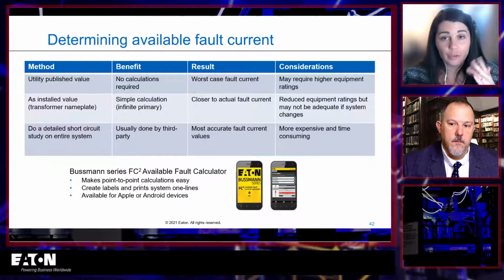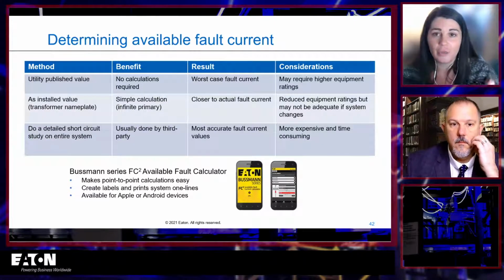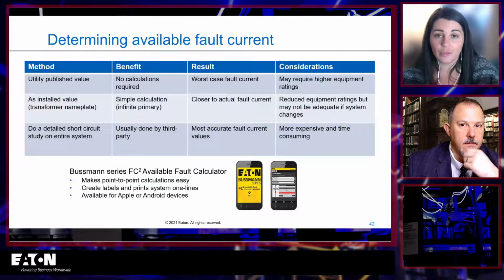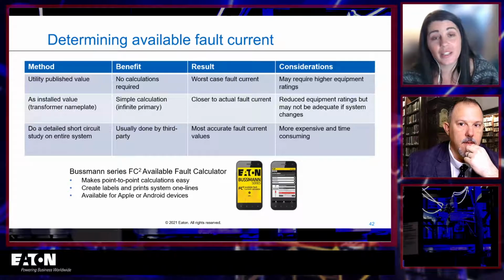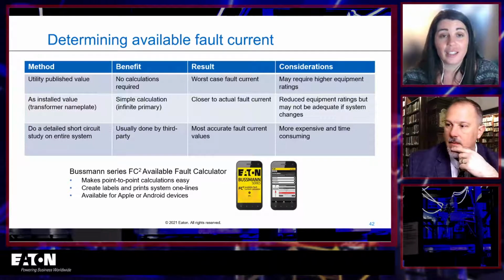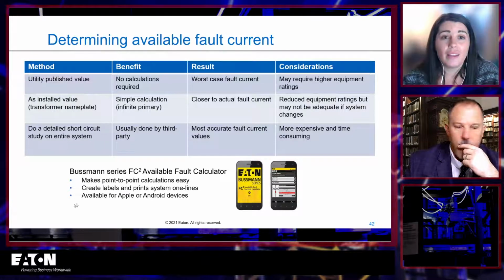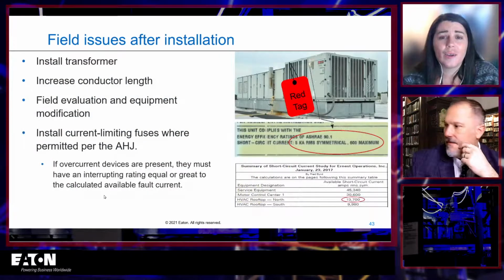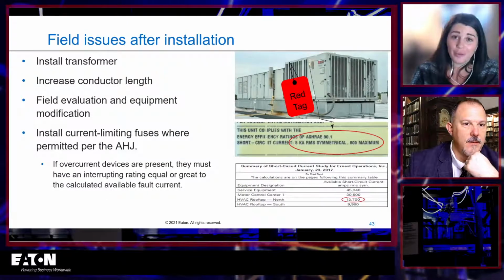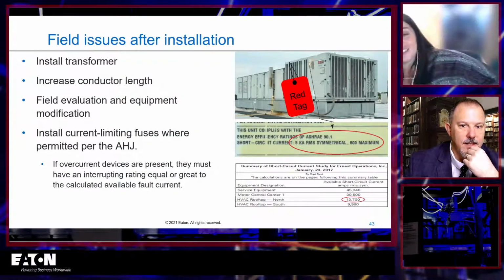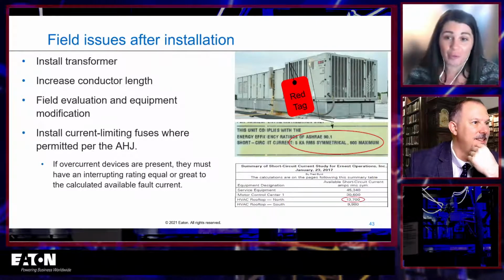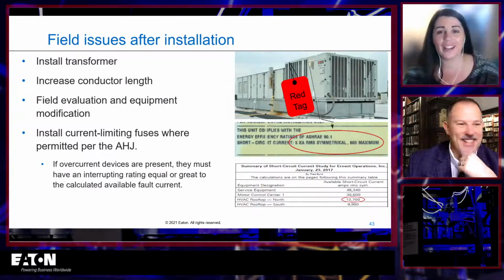If you're the owner of the facility, you might think about doing the detailed version. We will determine the available fault current. And now we go to the next slide. I believe there it is. We finally get to talk about what we do if we install a piece of equipment that has a short circuit current rating lower than the available fault current. So we're finally at that point.